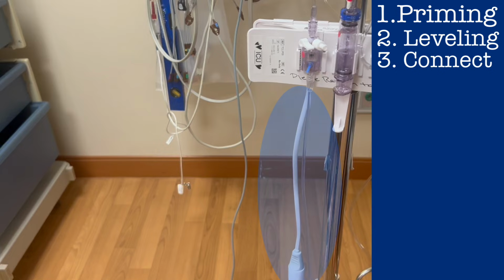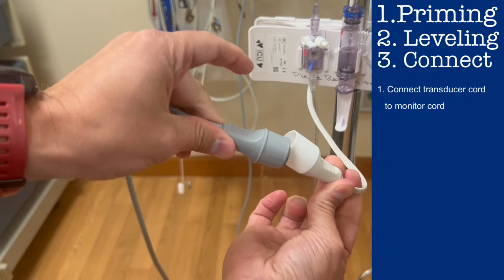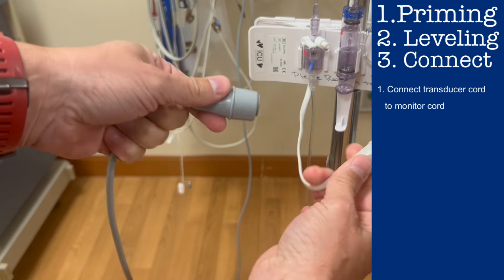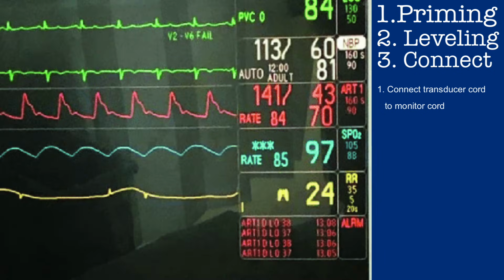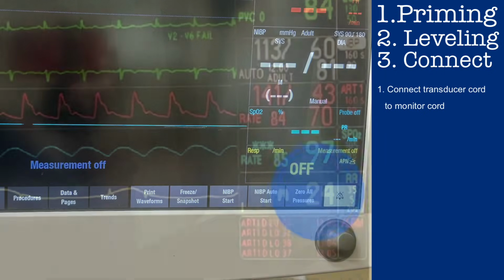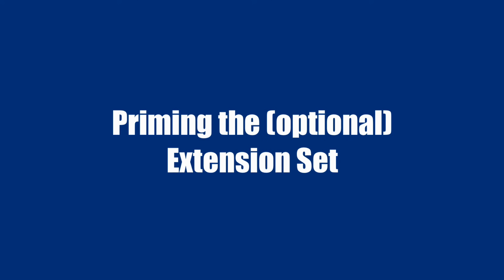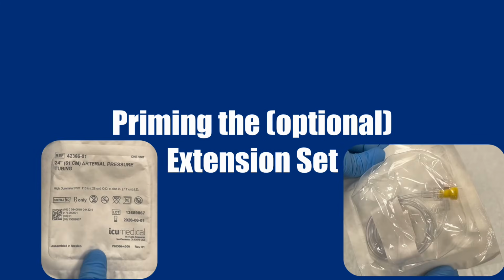Now connect the transducer to the monitor. Simply take the cord attached to the transducer and plug it into the corresponding cord on the monitor. Now, as soon as the line is placed and connected to the tubing, you should be able to see a waveform on your patient. At that point, you'll have to zero out the system. Now, if you are utilizing an arterial pressurized extension set, you'll need to prime that as well, but you'll do that during the line placement procedure. Line placement is a sterile procedure, so connecting the extension set will require sterile technique.